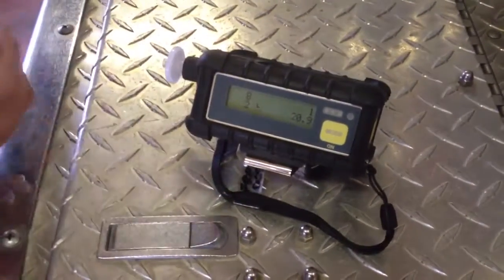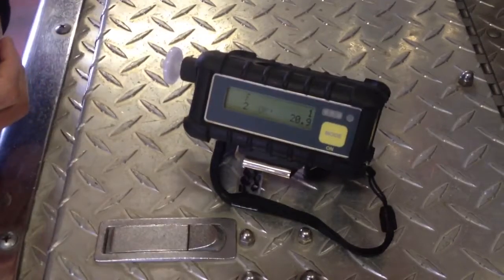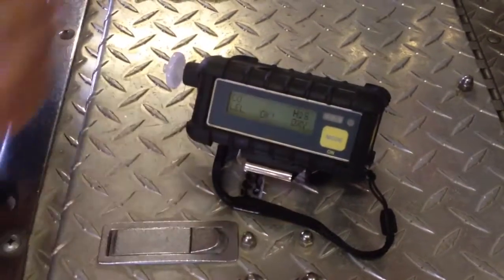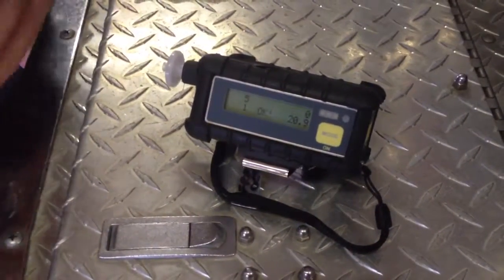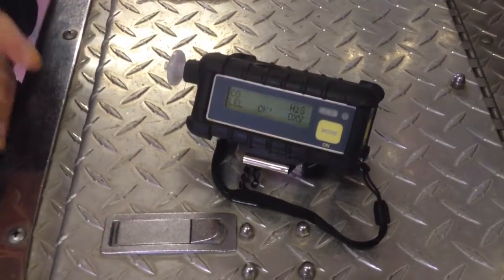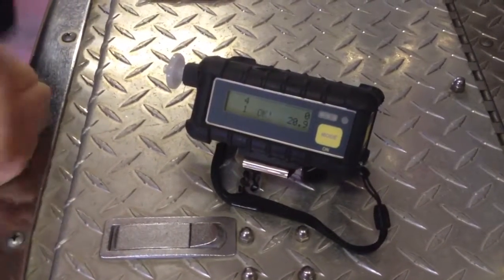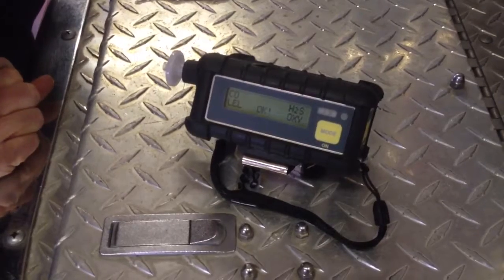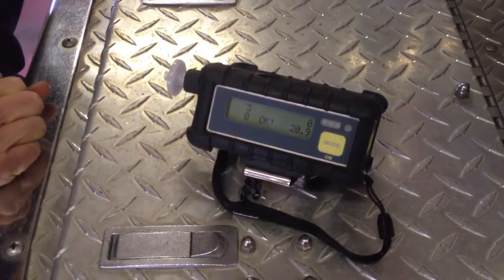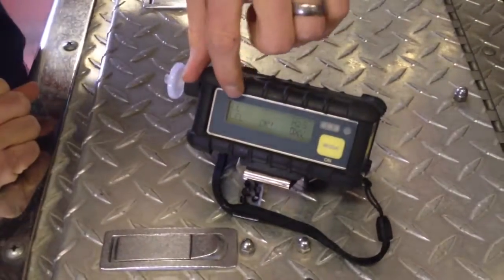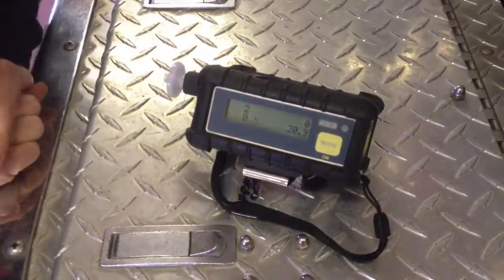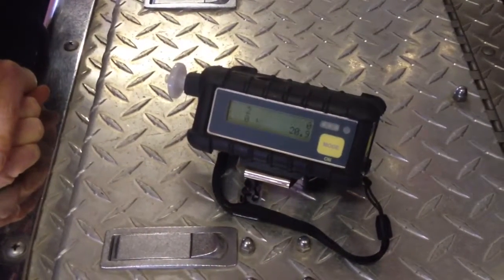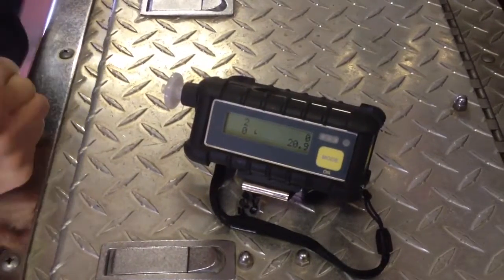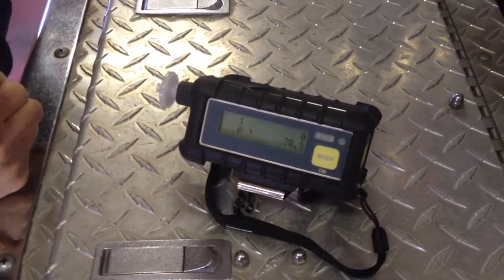Now what we have to do is wait, just until these sensors come back down to 0. They may come down to a point where they're reading like 1 or 2, and that's okay too, but get as close to 0 as you can, along with our 20.9 reading. You let that sit for a couple minutes after you're done, and then you're ready to go.